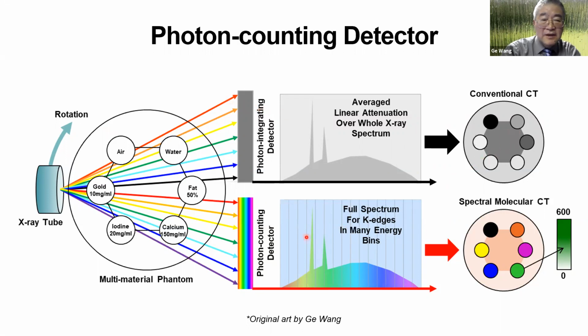And with the latest technology, we use a photon-counting detector. You detect each individual photon one by one, and you also know the energy level. So we can know whether the X-ray photon is a soft X-ray or a hard X-ray, and we can put each detected photon into the corresponding energy bin. So we add a spectral dimension to X-ray measurement. Then we can reconstruct colorful X-ray CT images. So this is the benefit of the photon-counting detector.